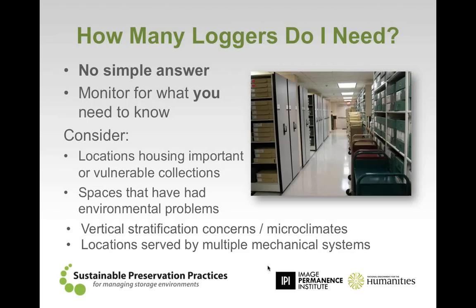Do you have high shelving and you're afraid of vertical stratification? Then you can keep a logger on the low shelf, the middle shelf, and the high shelf to look for these things, maybe even find possible microclimates. People have also asked, can we do a site survey and log in multiple storage areas and find out which storage area is best? That's an idea as well.